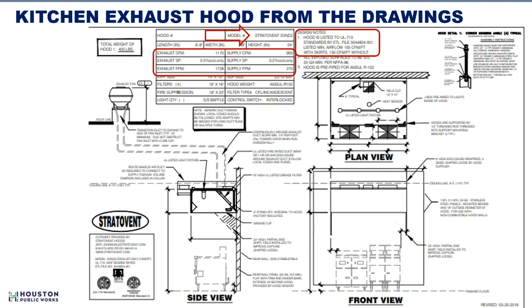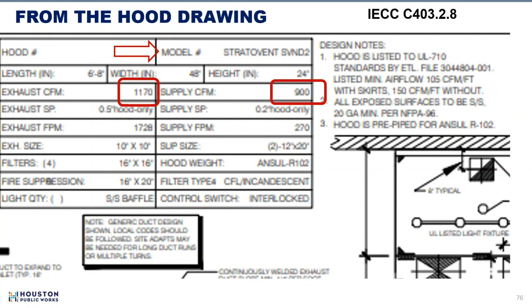Let's take a look at a kitchen exhaust hood from the drawings. Pretty entertaining. So there's kind of that story. There's like a cut-through view of it, blah, blah. So this one had the model number and exhaust CFM and supply CFM, etc. In the provision, it says replacement air introduced directly into the exhaust hood cavity shall not be greater than 10% of the hood's exhaust airflow rate. So back of the napkin here, exhaust CFM 1170, supply CFM 900, looks like 77% of exhaust. That's way more than 10%.